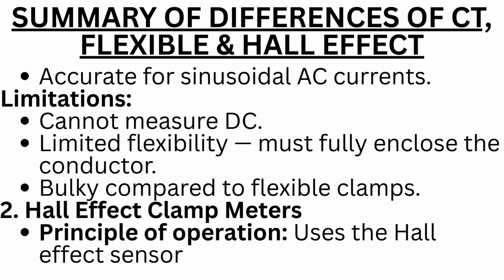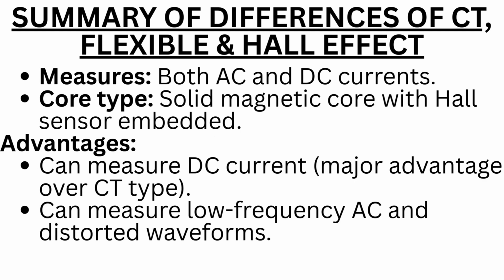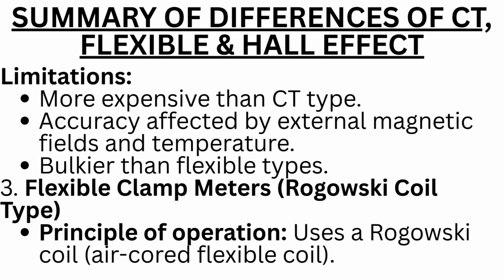2. Hall effect clamp meters. Principle of operation: uses the Hall effect sensor. Measures both AC and DC currents. Core type: solid magnetic core with Hall sensor embedded. Advantages: can measure DC current, a major advantage over the CT type. Can measure low frequency AC and distorted waveforms. Limitations: more expensive than the CT type. Accuracy affected by external magnetic fields and temperature. Bulkier than flexible types.